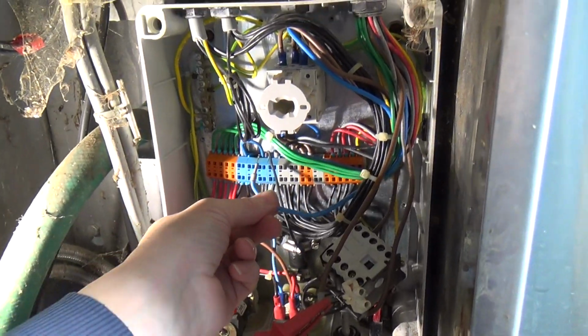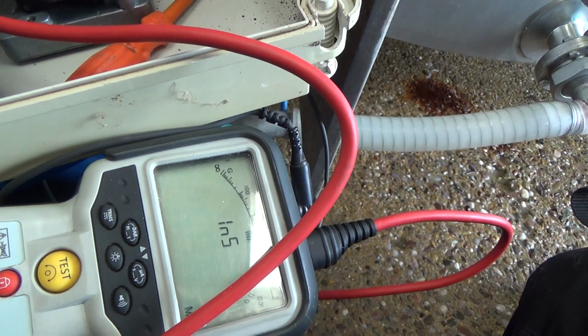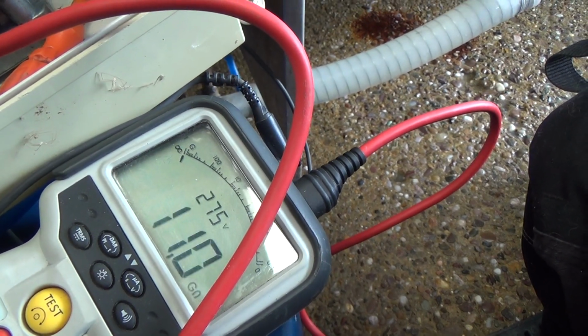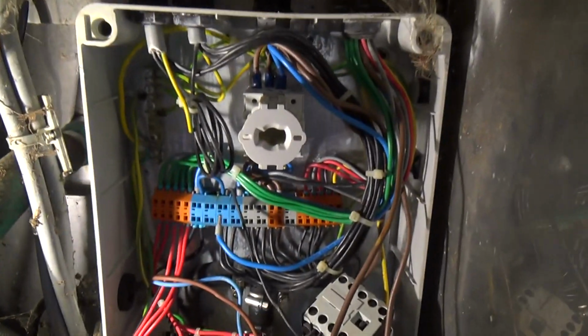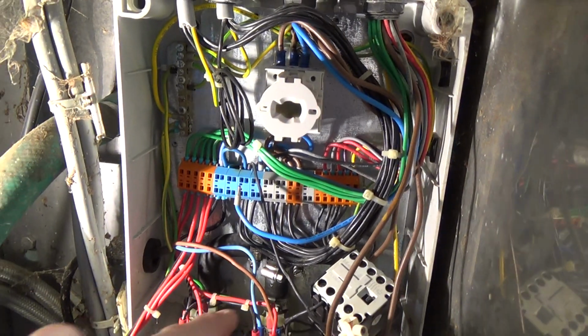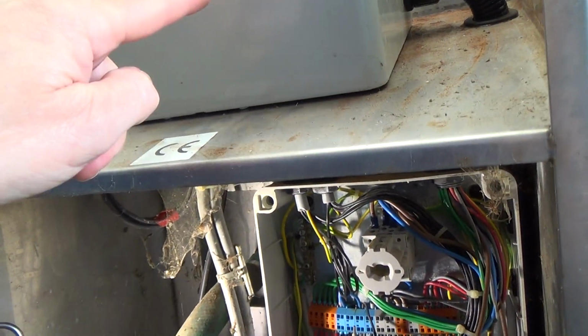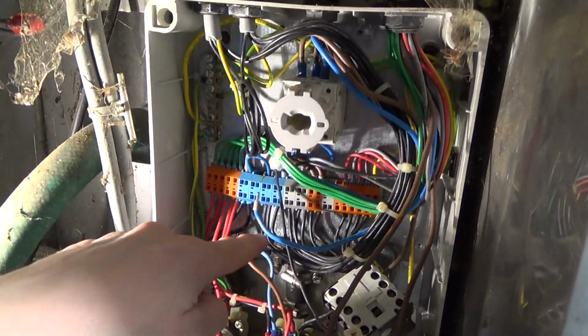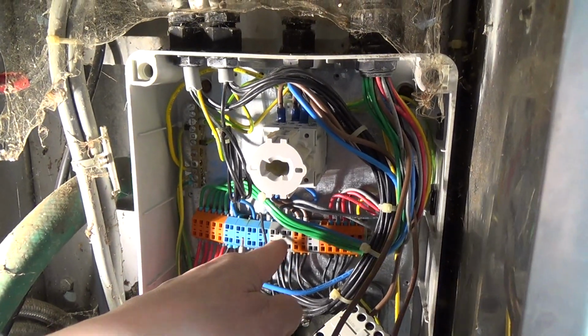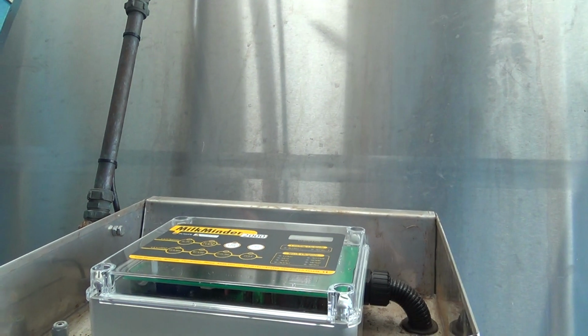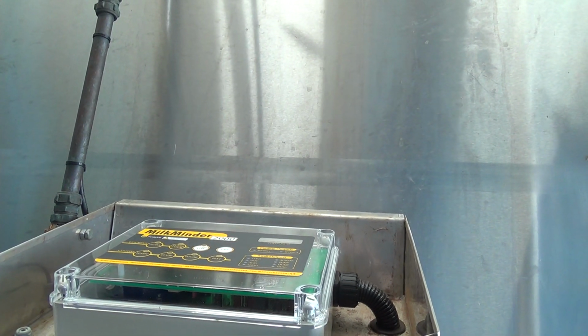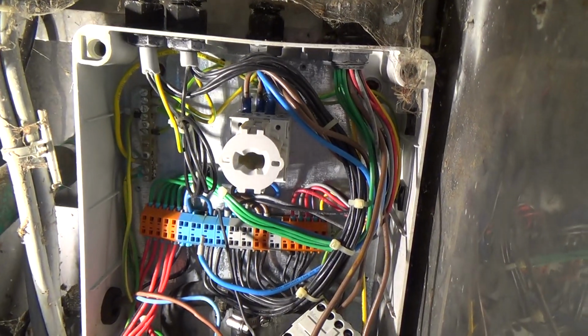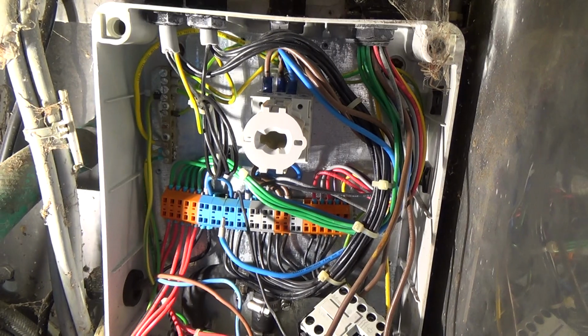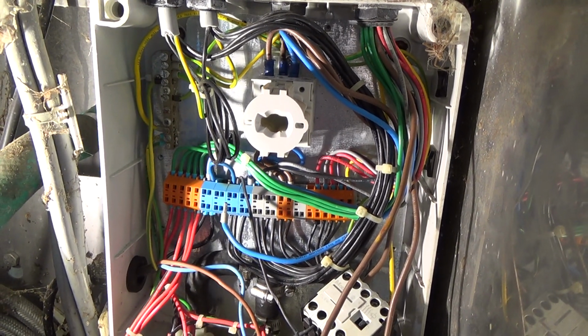Okay, so we've popped that neutral out of there, and then we're back on that brown wire where we had the short to start with. There we go, 11 gigaohms, so that's fine. So all we were doing was tracing going up that live, through the neutral, through the transformer, up the live into the transformer, down the neutral, and then into there, and then up that neutral on the black wire all the way out to the control box in the loft. And then from that control box down to wherever his breaker board is, and then from that breaker board out the way to the main poles where his earthing is, you know, where the earthing's done. That's what we were finding as a fault.